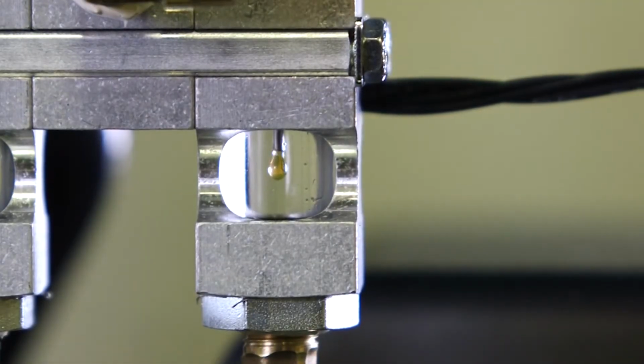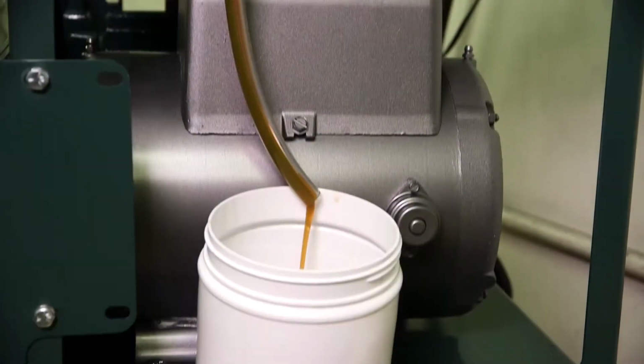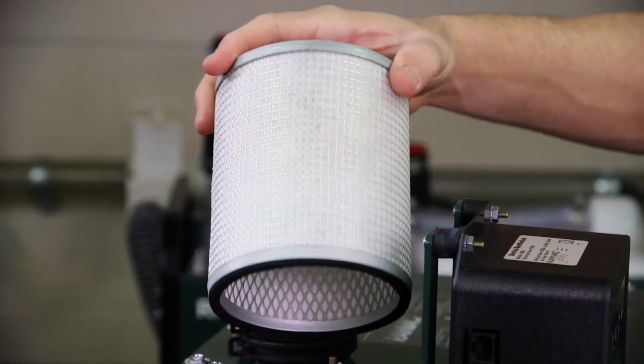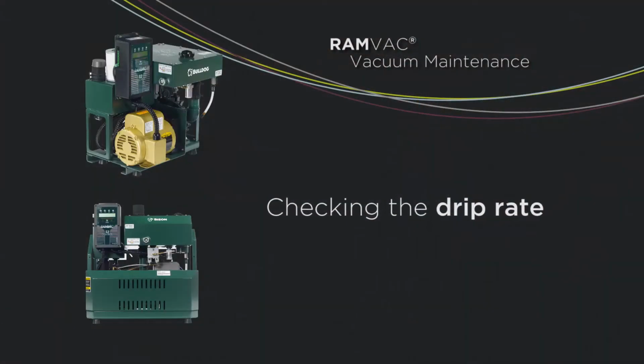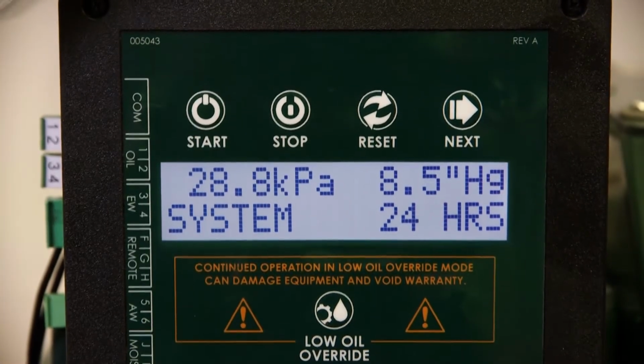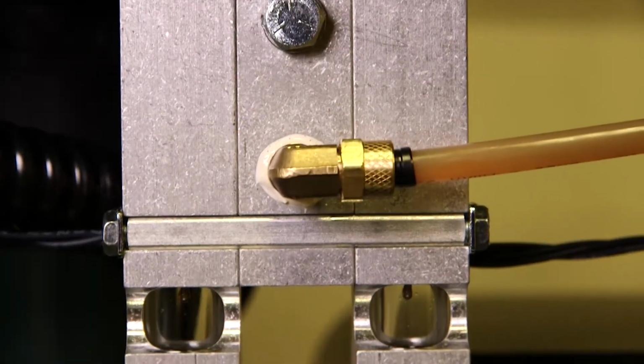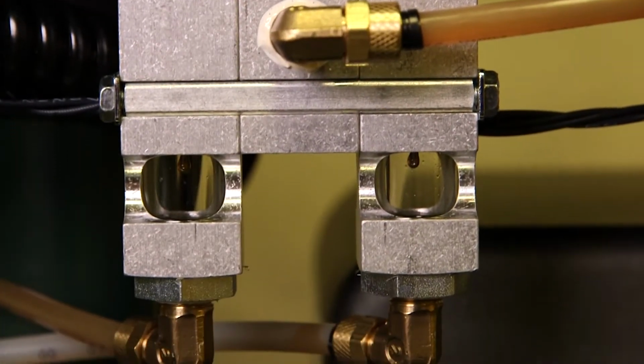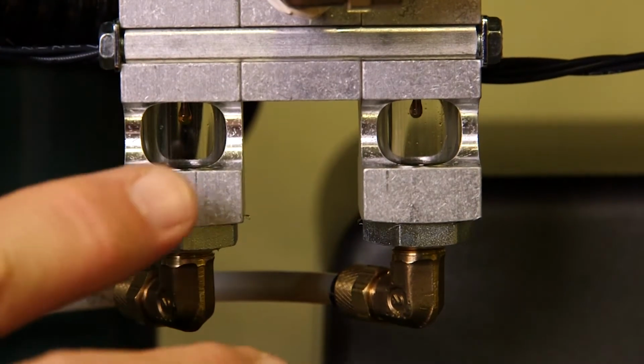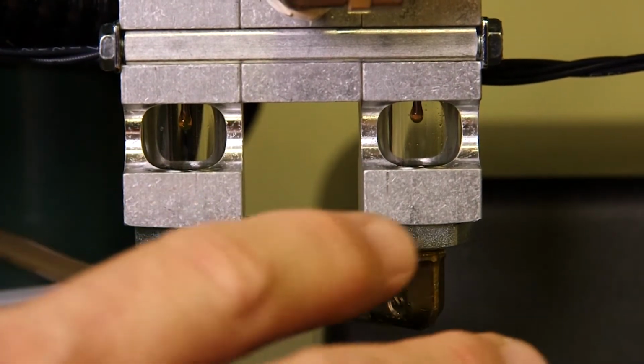Continue watching for details on how to check the drip rate, change the oil, and replace all filters. Checking the drip rate. The first step is to start the vacuum and run for at least 10 minutes. Second, look through the sight glass on the bottom of the drippers to check for drips of oil. Next, count the drips of oil through each sight glass per minute.